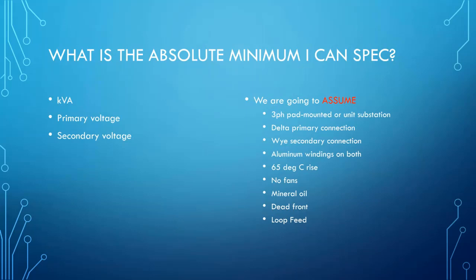We're going to assume that it's a delta primary and a Y secondary connection. We're going to specify aluminum windings on both the primary and secondary. We're going to assume 65 degrees C rise. We're going to assume that you don't want any fans on the transformer. We're going to assume that price is an issue, so we're going to quote this with mineral oil. We're going to quote dead front because I like to always err on the side of safety, and there's really no adder for quoting a pad mounted transformer with dead front bushings. And I'm going to quote it as loop feed because it's a very, very small adder to get those extra three bushings, and then you have a place to put arresters, or if you ever find yourself needing to loop out of that transformer, you now have the capability to do so.